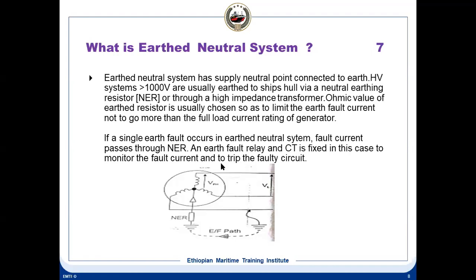So if a single earth fault occurs in the neutral earth system, suppose there is one earth fault taking place, the fault current will pass through the NER. An earth fault relay or a CT, that is a current transformer, will monitor it, because the current transformer keeps monitoring the current flowing through the NER, and it will give a trip to the faulty circuit. So these are the advantages of using an earth neutral system.